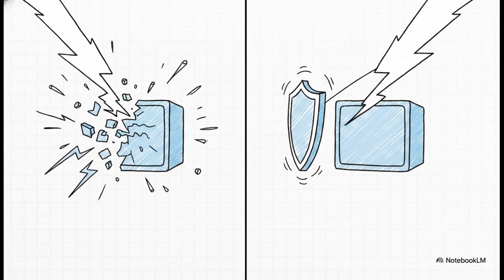You see, while vacuum contactors use incredible interrupter technology to control AC motors, transformers, and power factor correction banks, the contactor itself actually has a very limited short-circuit breaking capacity. Without fuses stepping in to intercept, a real short-circuit fault would instantly destroy the contactor, and honestly, potentially take the entire switchboard section with it. Fuses are absolutely mandatory in every marine installation to handle these massive fault levels. The contactor alone simply cannot break them.